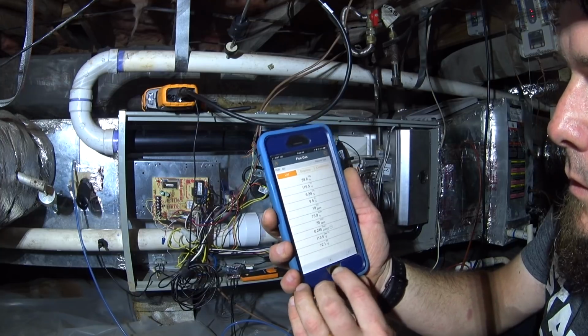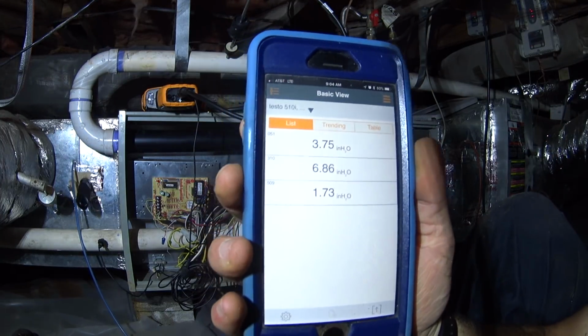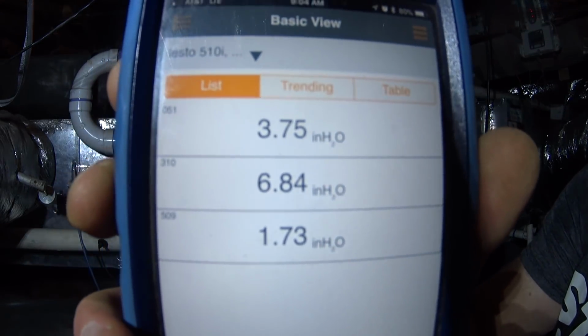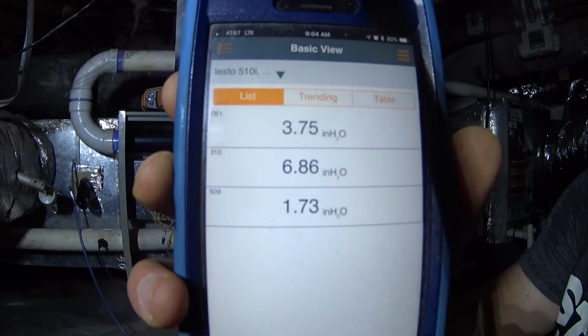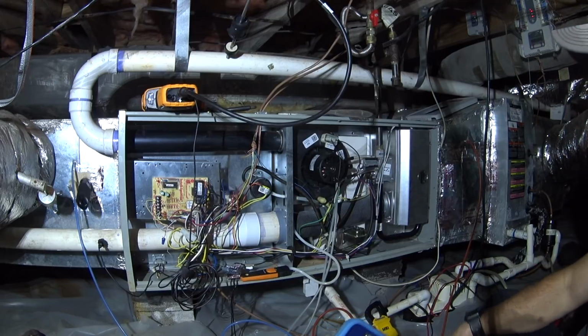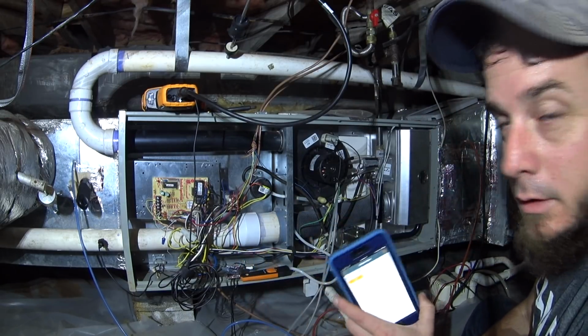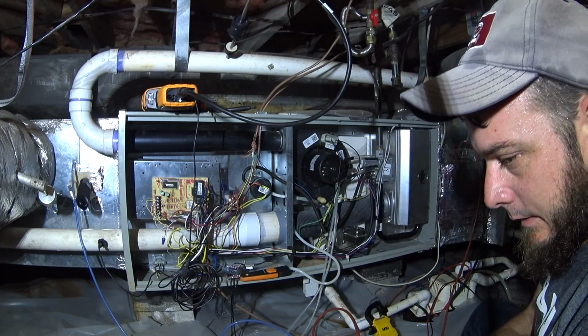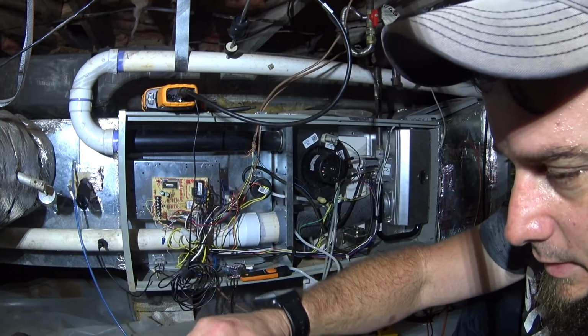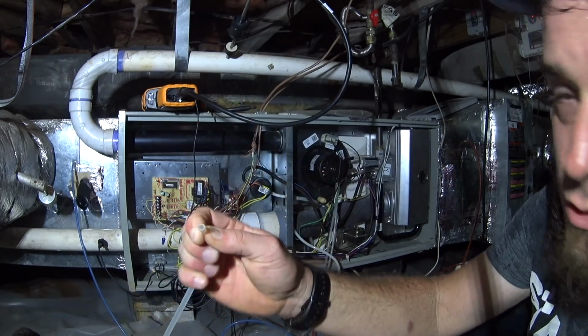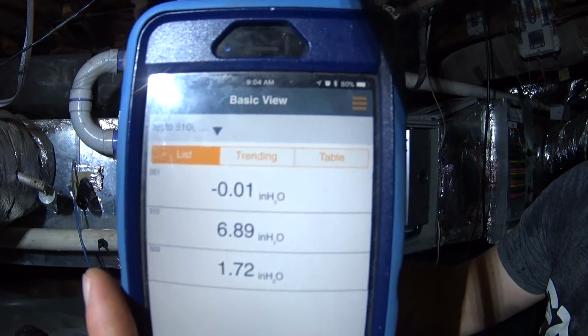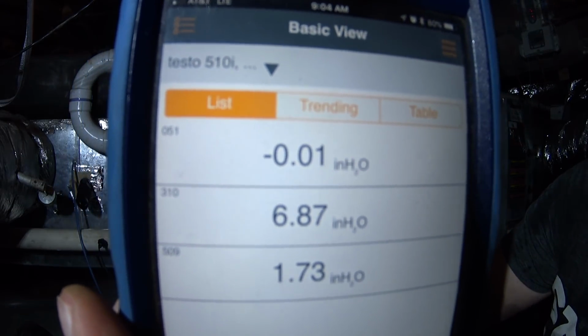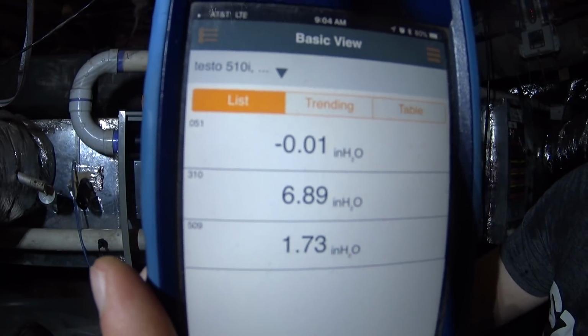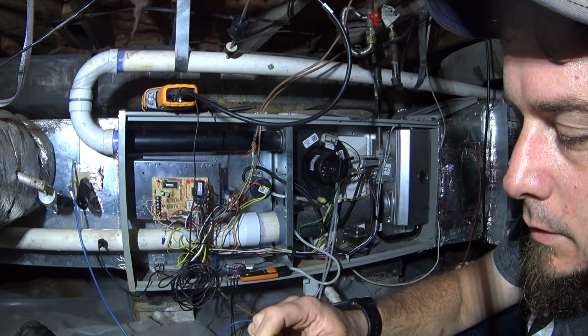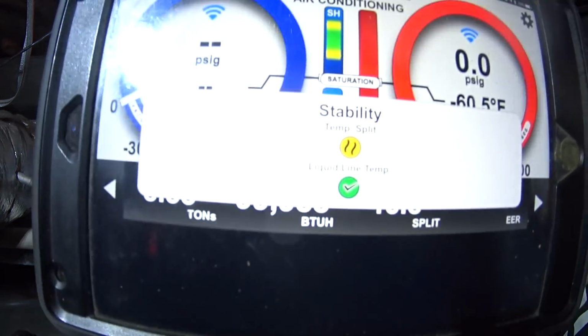Let's just check on our Testo smart probes or manometers again. We've got 3.75, 6.86, and 1.73. Those numbers are probably creeping a little bit because they tend to, but they're reasonably close to what I would expect at this point. To show that, I will disconnect the outlet gas pressure while I'm pinching the hose and show you that we've got a creep of about negative 0.01 and it moves to about 0.02, so it's creeping slightly from where it was zeroed initially.